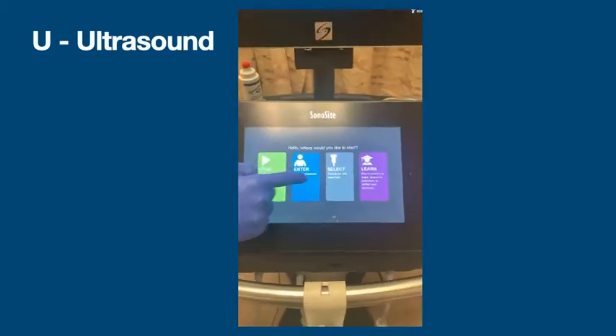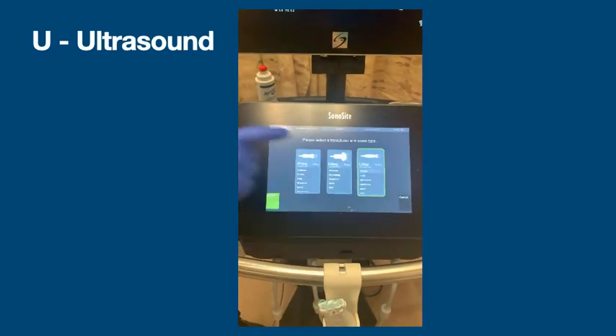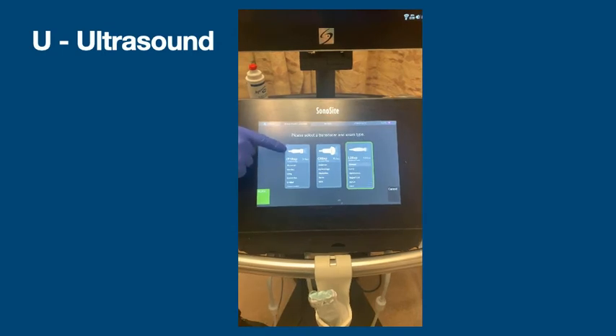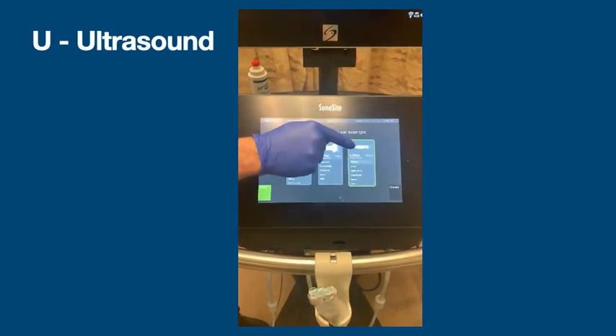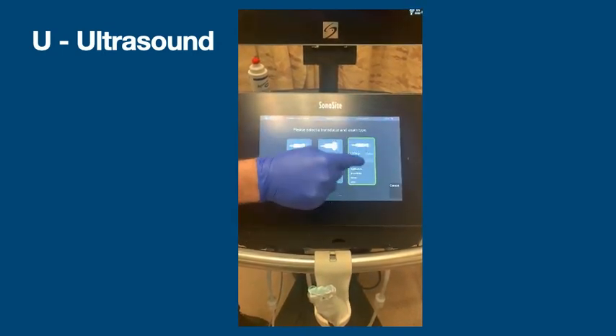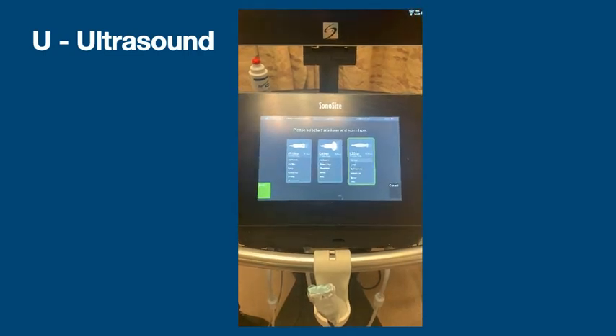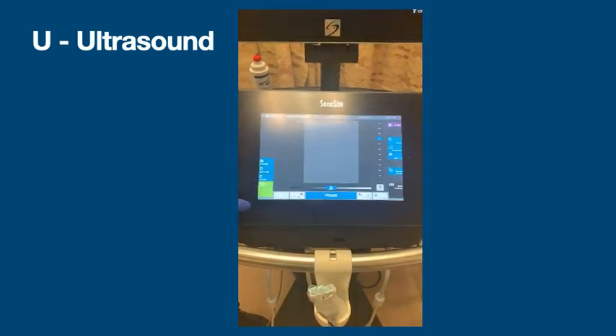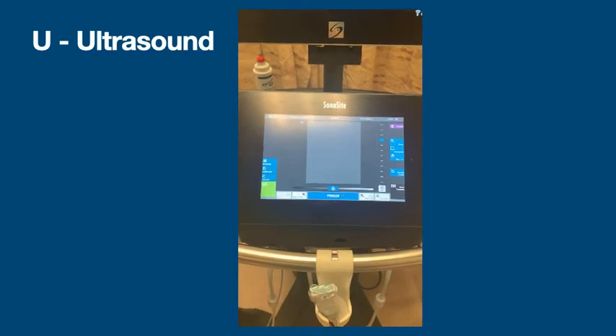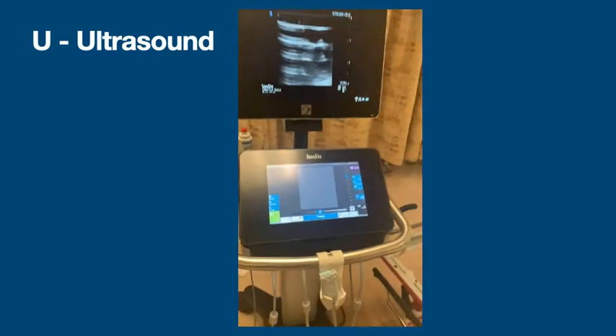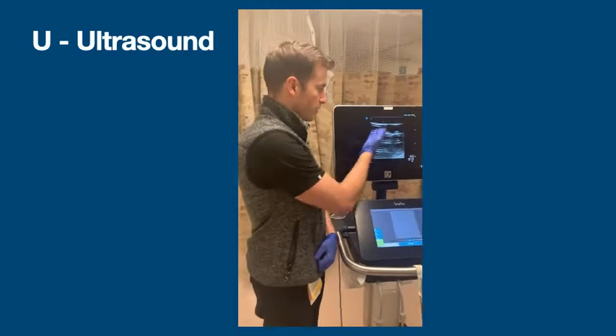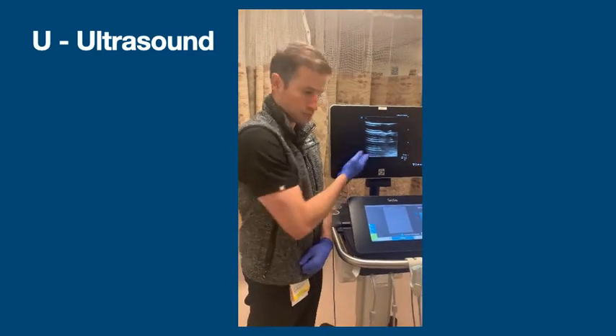The third selection over is the select transducer. You're going to poke that one, and then you get all these different types. Phased array, curvilinear, this is the linear probe. Just select the venous setting. Sometimes it'll automatically open up, sometimes you need to hit scan. So now we're into the actual scanning process of using the ultrasound. You can see that we're already seeing ultrasound waves up here conducting through the medium.